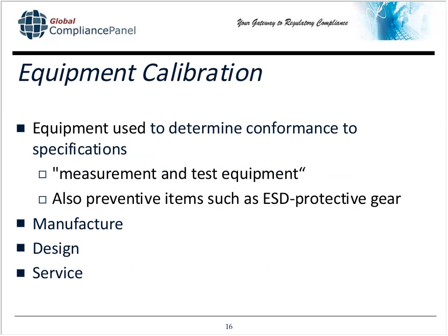Moving from validation to calibration, calibration is the situation where you want to make sure that any piece of equipment that you use to determine conformance to specification is accurate in its measurement. Something that's interesting is that many firms are really well aware of the need to include production and QA equipment in their calibration program, but some forget to include equipment used by R&D, research and development. They're developing your processes and your specifications. Because it's R&D that often translates customer requirements to physical and performance specifications in the early stages when they're doing design control.